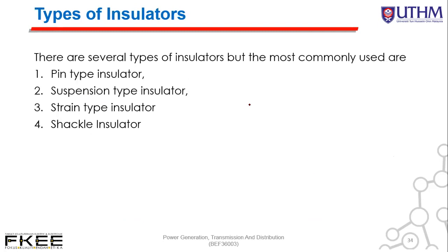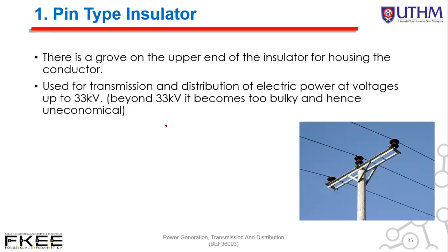There are four types of insulators: pin type, suspension type, strain type, and shackle insulator. The pin type insulator has a groove on the upper end for housing the conductor. It is used for transmission and distribution of electric power at voltages up to 33 kV only. Beyond 33 kV it becomes too bulky and hence uneconomical.